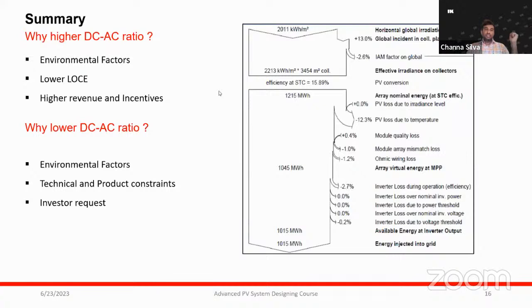And why go for a lower DC to AC ratio? If you look at that, of course, lower temperatures. And one main thing is high elevation, places close to mountains and similar high altitude locations. In those locations, irradiance is quite higher than standard test conditions.